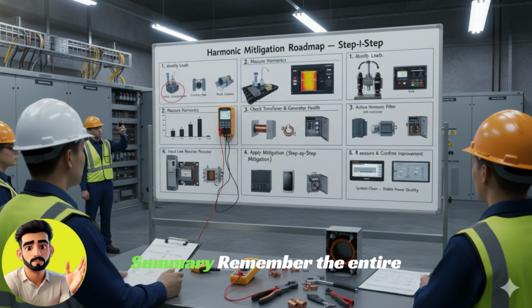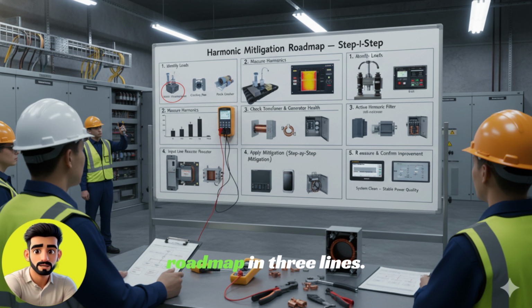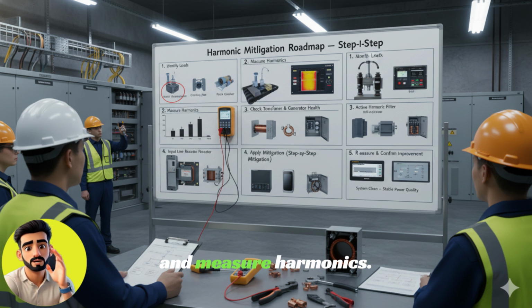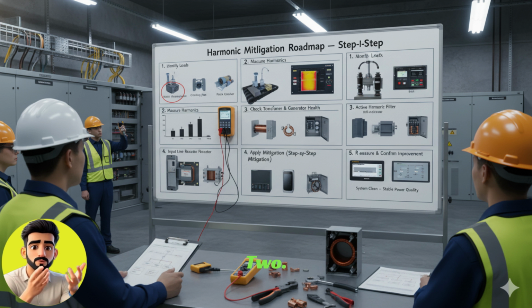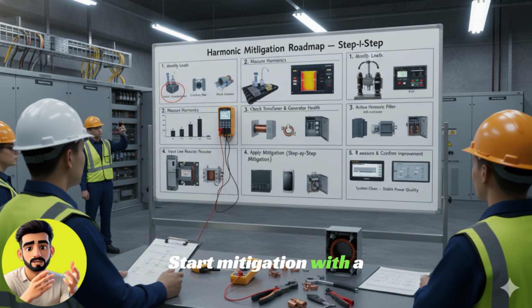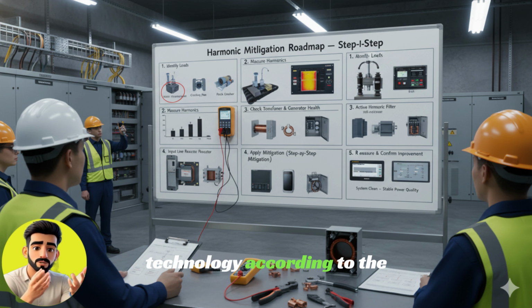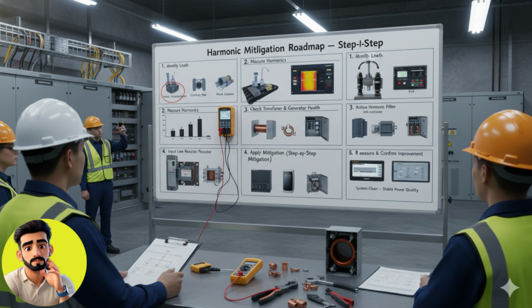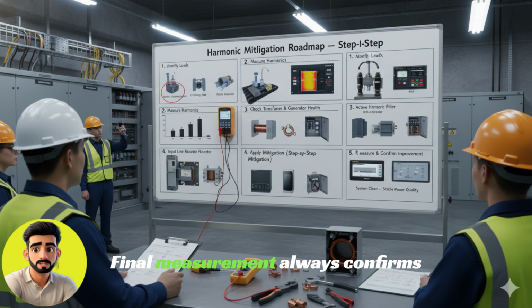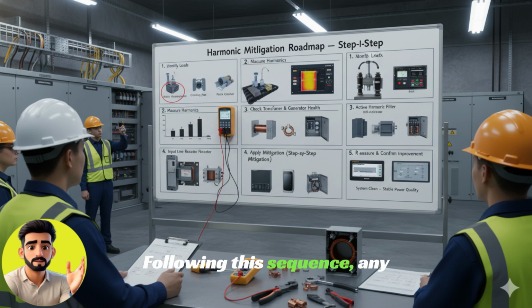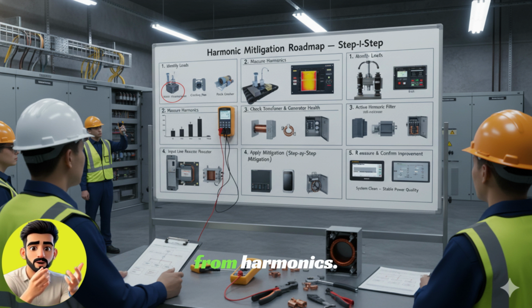Summary. Remember the entire roadmap in 3 lines. 1. First, understand the load and measure harmonics. 2. Start mitigation with a line reactor and select the filter or drive technology according to the problem size. 3. Final measurement always confirms that the system has been cleaned. Following this sequence, any plant can be safe from harmonics.